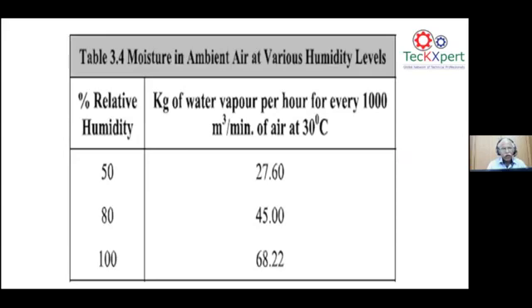We can see for a given ambient of 30 degrees, at 50% RH or 80% RH or 100% RH, the kg of water goes from 27 to 68. So the water vapor per hour for every 1000 meter cube per minute, the increase in rate is very high, especially when the relative humidity of the ambient surrounding the compressor is a critical input. This needs to be monitored so that water ingress is not there in your compressed air line.